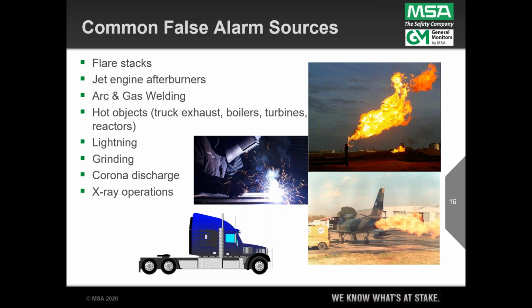Now, corona discharge, that's a UV-only source. That's from when a high voltage conductor begins to have a breakdown in insulation resistance, and it can actually glow. That glow is what corona discharge is, and I'll leave it at that. Also, X-ray, any nuclear radiation, is going to have energy that's going to be detected and sensed by a Geiger-Müller UV phototube, because they are not impervious; they are sensitive to that energy. So there's a quick rundown there.